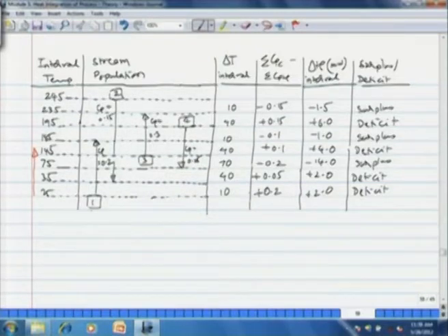Stream 1 goes from 20 to 180, so the shifted temperature interval is 25 to 185. Stream 2 goes from 250 to 40, so in shifted temperature it is 245 to 35, and I have also written here the CP values against these arrows. The arrows show the range of the streams in the temperature intervals, and the CP values written against the arrows are the heat capacity flow rates.